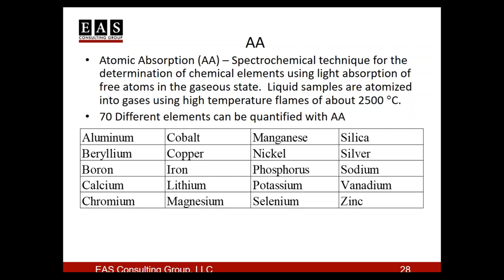So AA is atomic absorption. Basically here you heat up a liquid sample in a flame that gets to approximately 2500 degrees C, and the samples are atomized, and then you detect them in that fashion. This works for some 70-odd different elements. I've just listed a few here that we commonly see in dietary supplements.